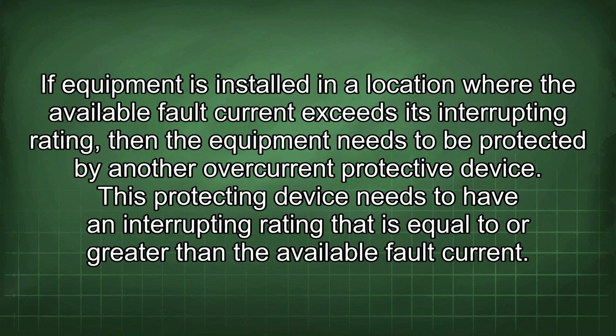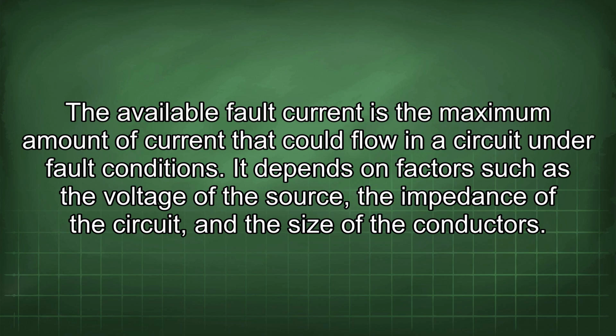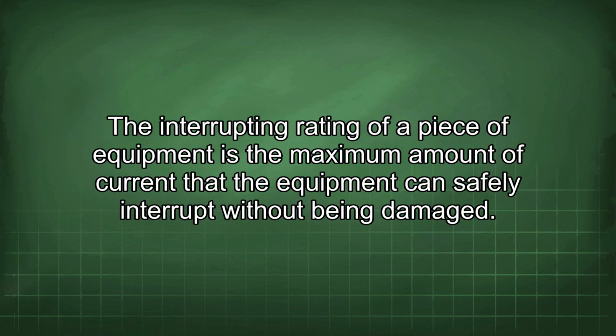If equipment is installed in a location where the available fault current exceeds its interrupting rating, then the equipment needs to be protected by another overcurrent protective device. This protecting device needs to have an interrupting rating that is equal to or greater than the available fault current. The available fault current is the maximum amount of current that could flow in a circuit under fault conditions. It depends on factors such as the voltage of the source, the impedance of the circuit, and the size of the conductors. The interrupting rating of a piece of equipment is the maximum amount of current that the equipment can safely interrupt without being damaged.